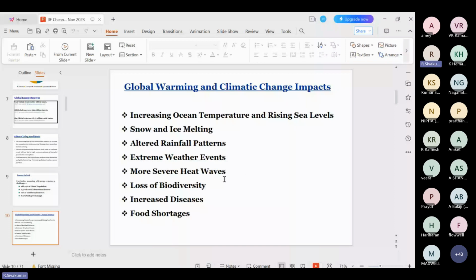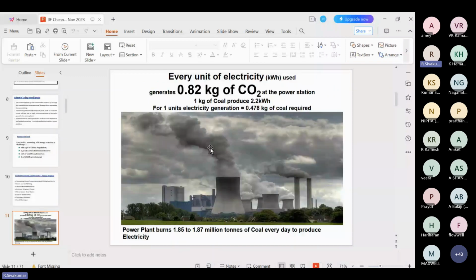See this picture, which typically comes from a power plant, a steam, boiler-based power plant. For every unit of electricity, 0.82 kg of CO2, carbon dioxide, is released at the power station. And every kg of coal produces only 2.2 units. So on average, a unit of electricity generation needs 0.478 kg of coal. Basically, the efficiency of our thermal power plants is very, very low. Only 30 to 35% is the maximum efficiency of our Indian steam-generating boiler plants.